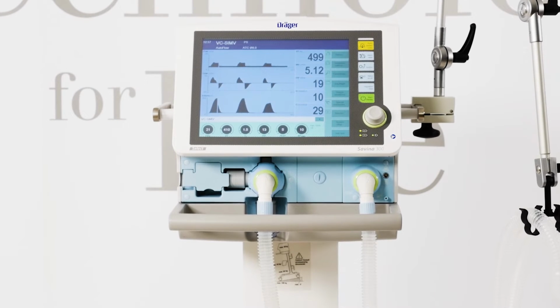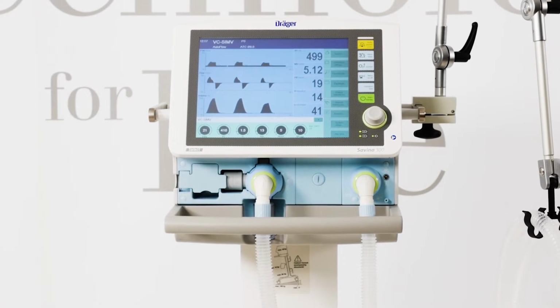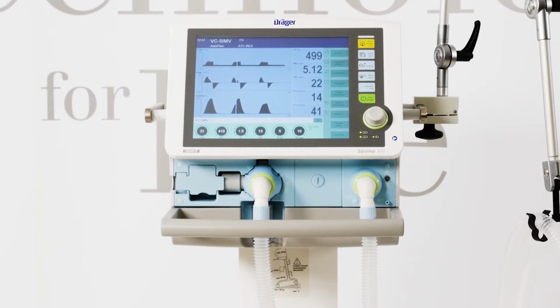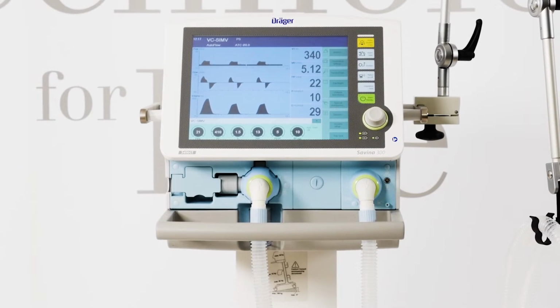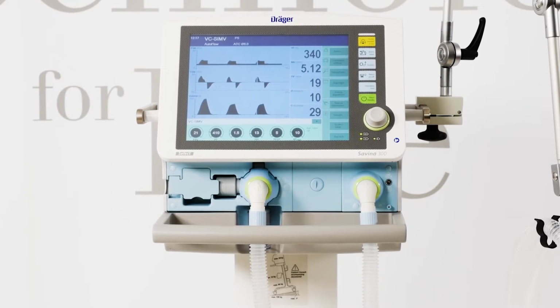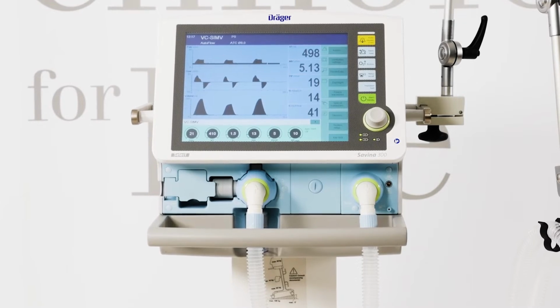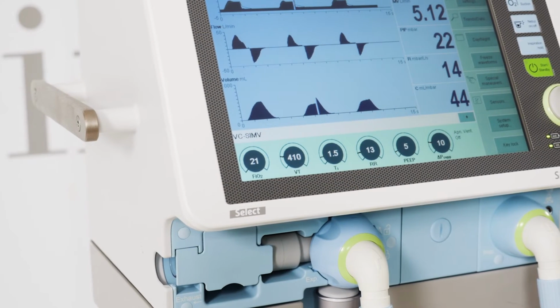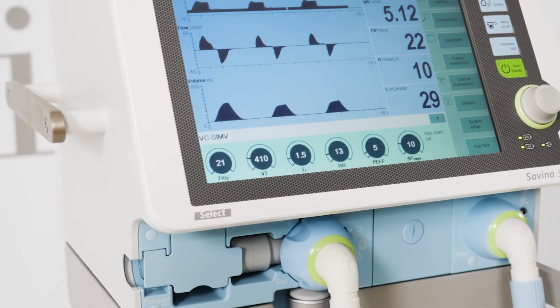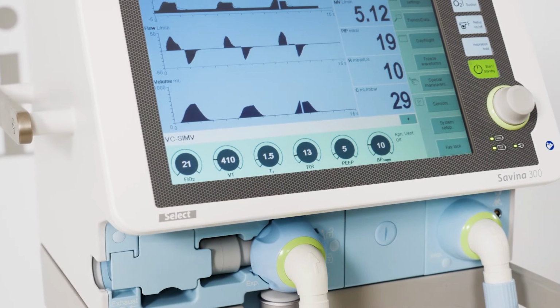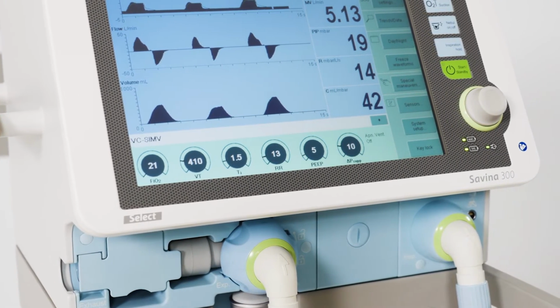Before using the device on a patient, readiness for operation of Savina 300 Select is checked during the device check and the breathing circuit check. Only start ventilation once the device check has been successfully completed. The device check is quickly and easily performed. Savina 300 Select guides the user through the respective test step in the form of a question-answer dialogue.